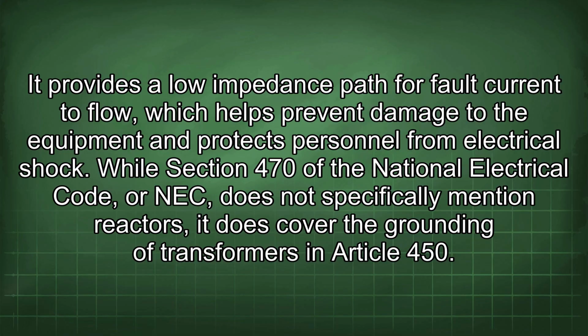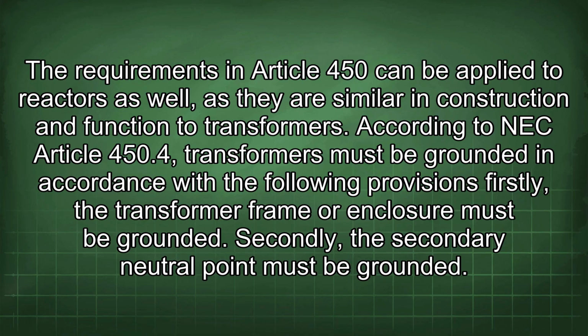does cover the grounding of transformers in Article 450. The requirements in Article 450 can be applied to reactors as well, as they are similar in construction and function to transformers. According to NEC Article 450.4, transformers must be grounded in accordance with the following provisions. Firstly, the transformer frame or enclosure must be grounded. Secondly, the secondary neutral point must be grounded.